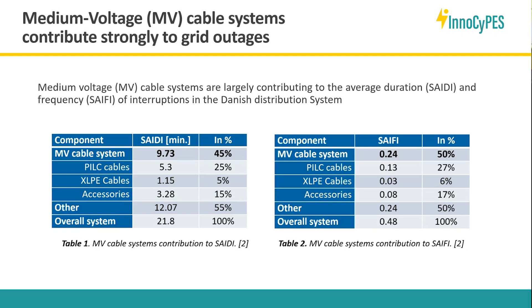So the first reason is that we have indexes that measure the downtime of components from a system level. So we say, what is the System Average Interruption Duration Index of all the components we have in the network, on an aggregated level. And that enables us to indicate some of the relevance. For medium voltage in Denmark, we can see that 45% of these indexes originate from cable systems. And we can look at another indicator, the System Average Interruption Frequency Index. This just counts the number of interruptions in the system, and there it's pretty similar. So this gives a first indication that we should look at this component category, because it actually contributes a lot to the things we want to avoid.